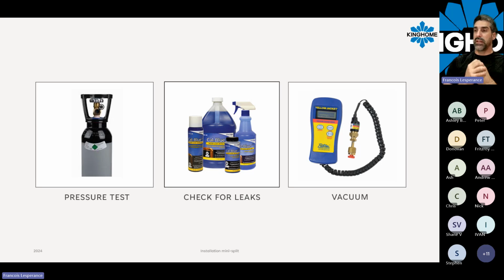When the connection is made, now it's time for pressure testing. It doesn't have to be a very large pressure test, just enough to make sure you don't have a big leak on your system before you try to pull a vacuum. You can also use soap on your flare nut to catch leaks if bubbles appear. You have to leave this soap on your flare connection for around 15 minutes to make sure the soap does its effect, and you can catch micro leaks, micro bubbles, if you leave it long enough. After that, when it's done, you will put a vacuum on the system.